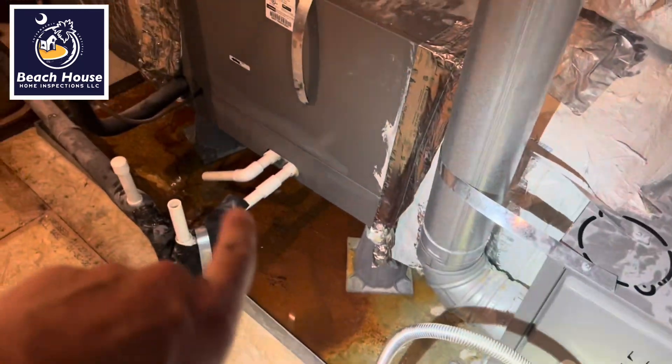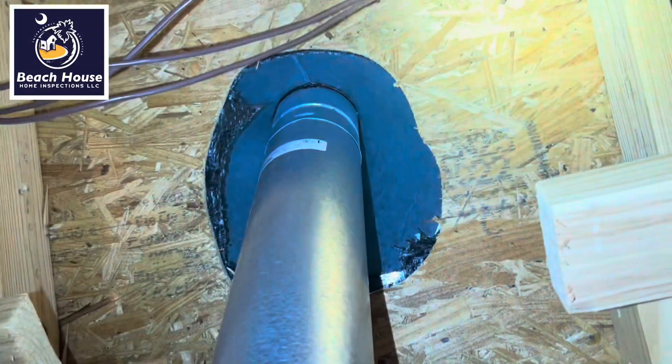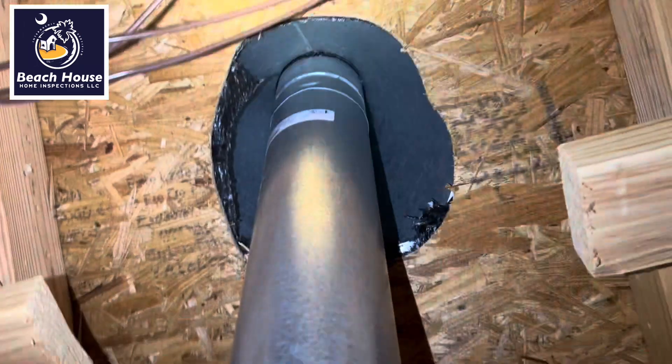HVAC guys have been out here two times and just can't seem to figure it out. This is a seismic strap that needs to be installed like this one. See that daylight? The seal between the flashing and the B-vent is improper — I can actually see moisture up there.